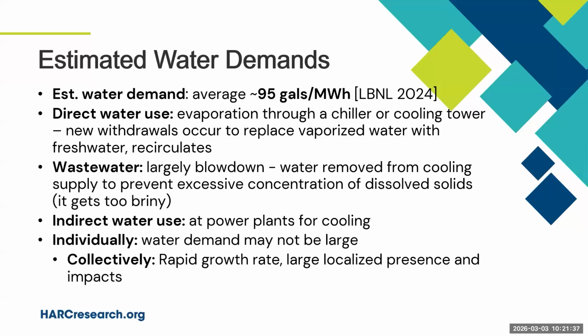So HARC used an estimate for water demand of 95 gallons per megawatt hour, developed by Lawrence Berkeley National Lab through their studies of cooling systems on data centers currently active, and used that to assess what the water demand could be in Texas.